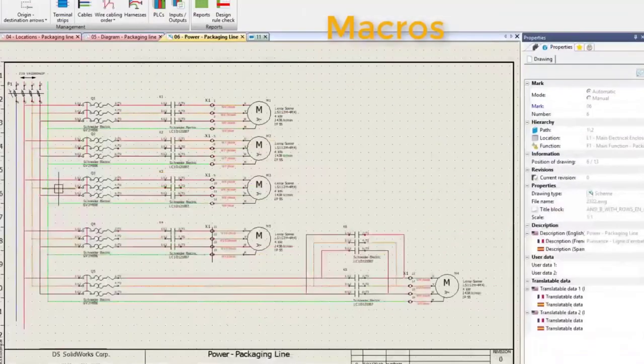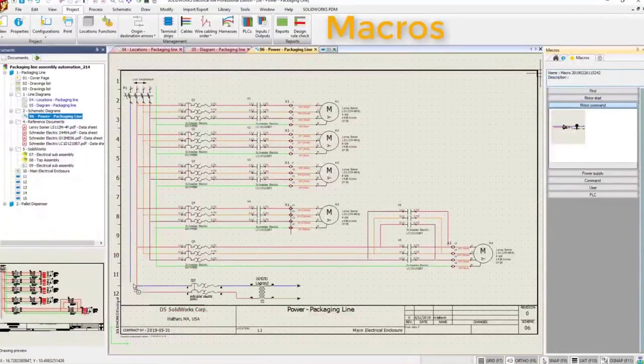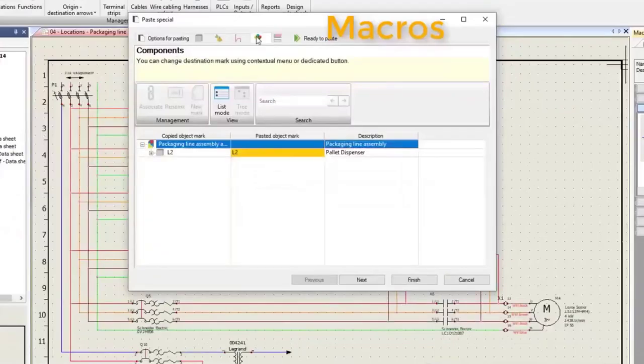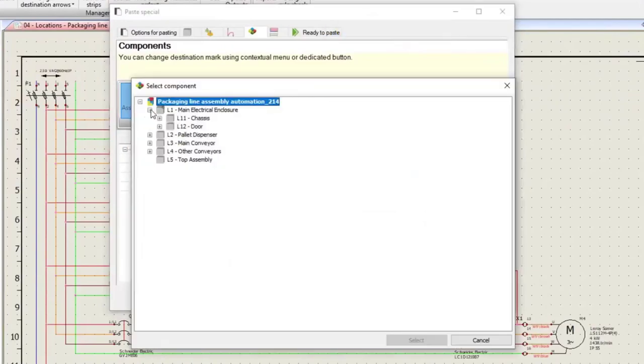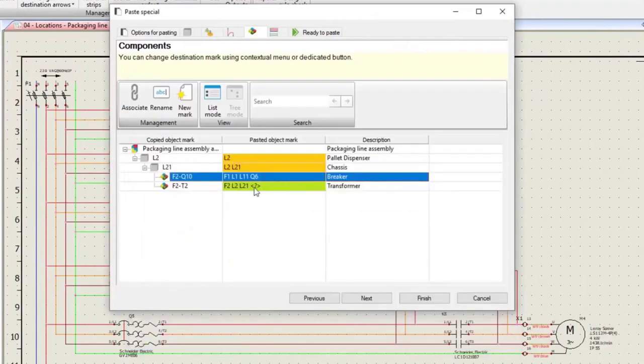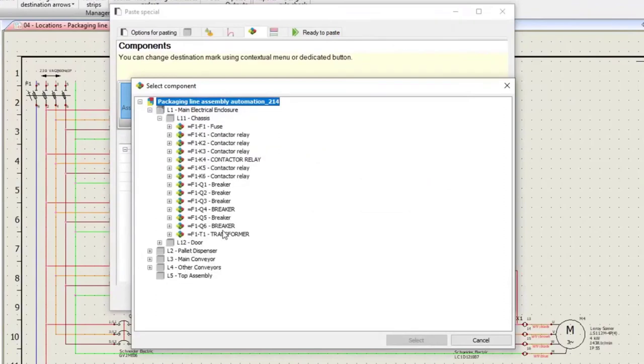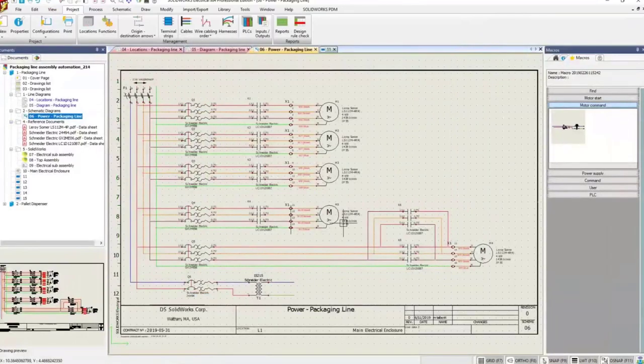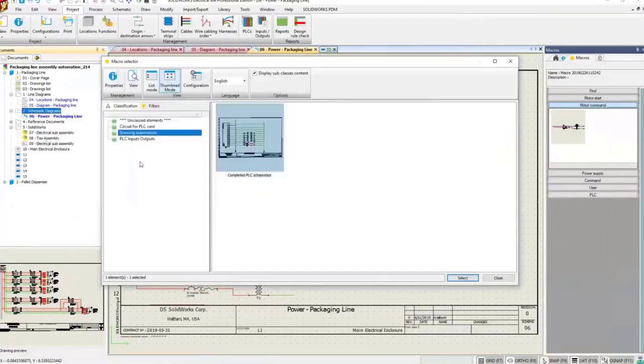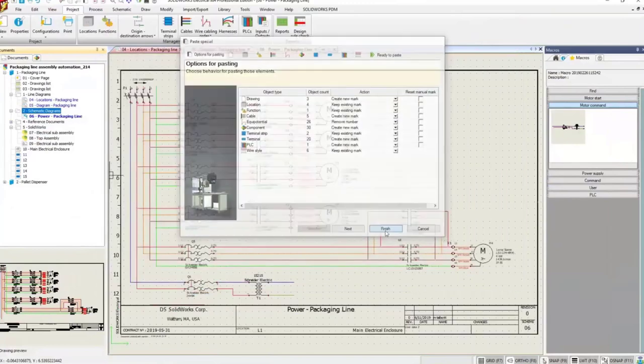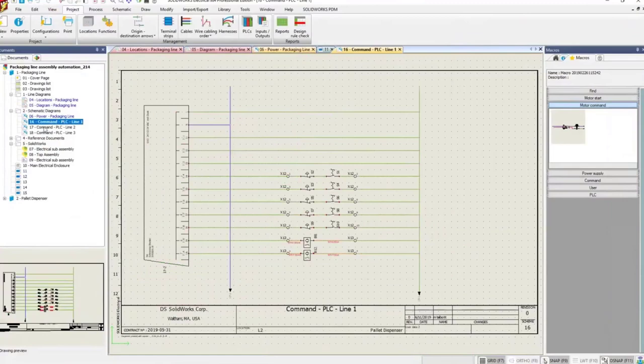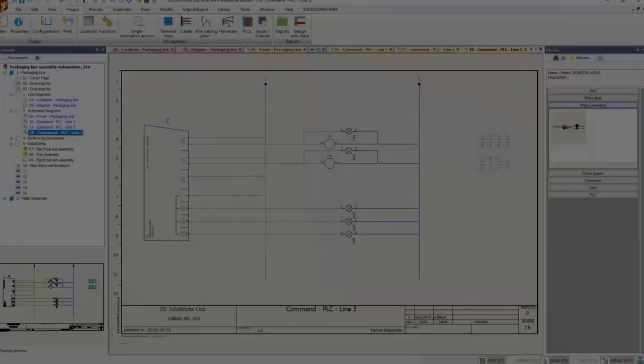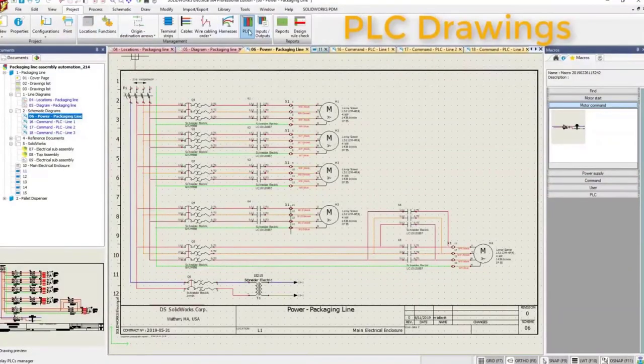Next, let's talk about macros. We define macros as a collection of any information that you want to be reused as a library entity. So here I've just pulled in a circuit of information, components, wires, cables, and I can then say, okay, let's use this information in context with this project. In other words, I've already used M1. I don't want you to give me M2. I want this to be tied to M1. Or maybe I do want you to give me M2. And the software will handle that automatically. We can also insert macros at a project level. In other words, we can insert schematics all in one go. In this case, I've inserted a PLC. That PLC was represented by three schematics. So now you can consider going towards modular design tools with project macros.